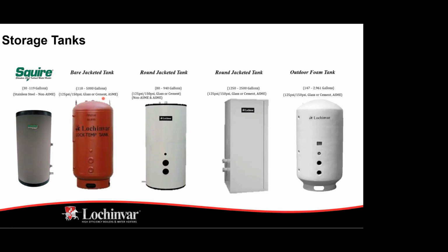The question is, do you need the tank insulated or not? And if so, do you want the factory to do that? You can insulate it either with foam and a jacket around it as round, or doing the same thing as square, or spraying it with some foam that's really designed only for outdoor use, not indoor. There are some fire concerns, off-gassing with a bare foam tank. So we wouldn't recommend sticking that inside a mechanical room. The other thing to be careful about is your max working pressure. You can get either 125 or 150, depending on where the tank's located and what pressures you're going to be seeing on your domestic side.